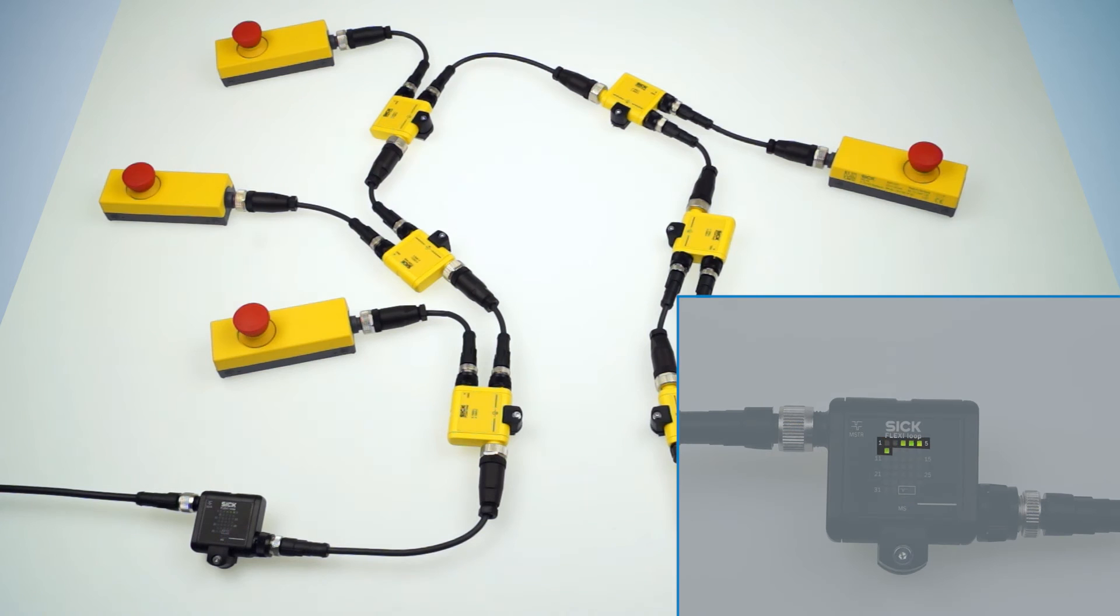With the help of the Node LEDs we can now check the effectiveness of the e-stops. The Node LEDs 3 to 6 are constantly green. Everything is fine here.